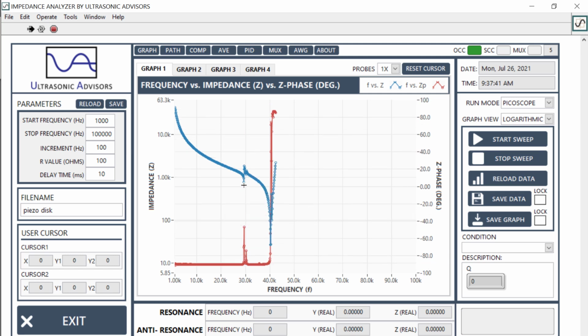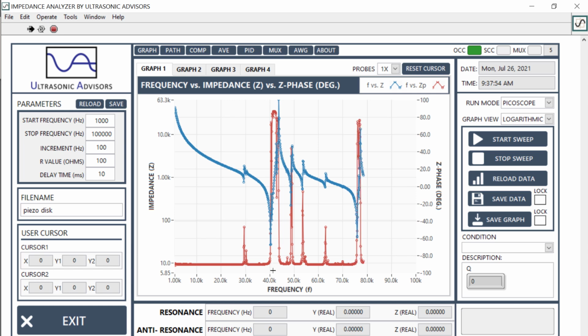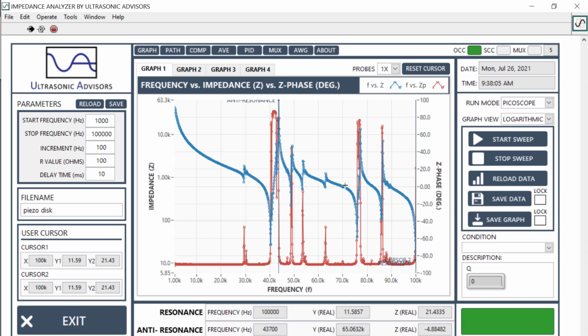So we have a lower resonance frequency, and we have several other modes as well. The main operating mode is at 40 kilohertz. These other modes here are either related to the bolt resonance, or there are other bending resonances which occur, which are symmetric and also antisymmetric or asymmetric. But this is a kind of typical range.